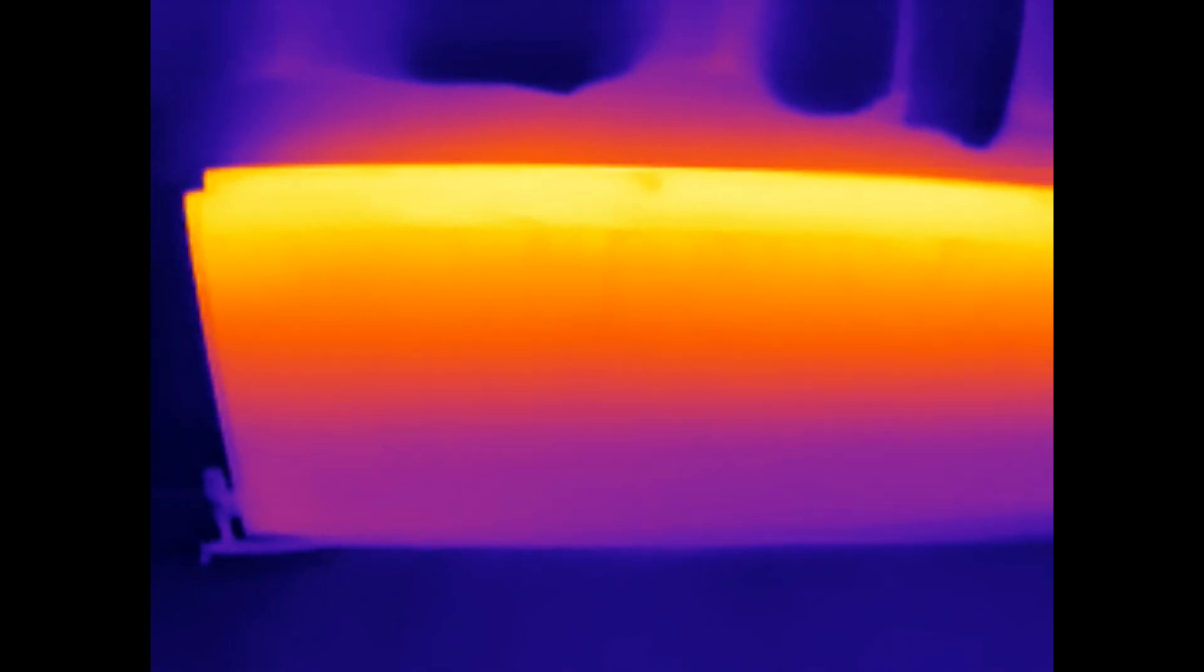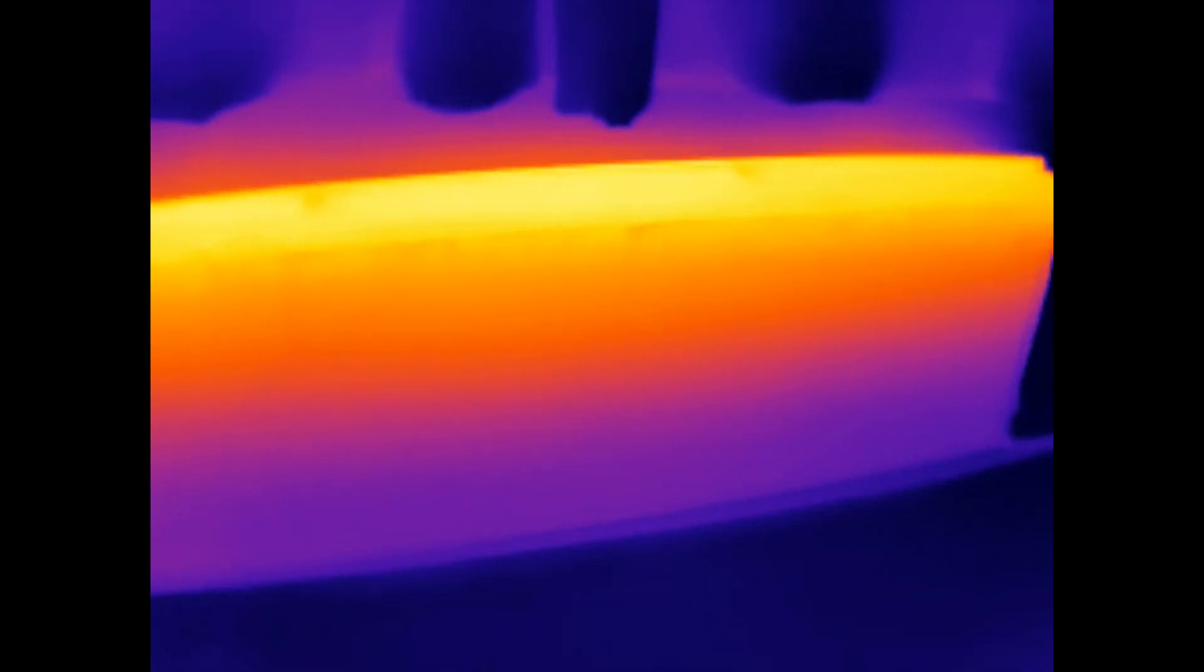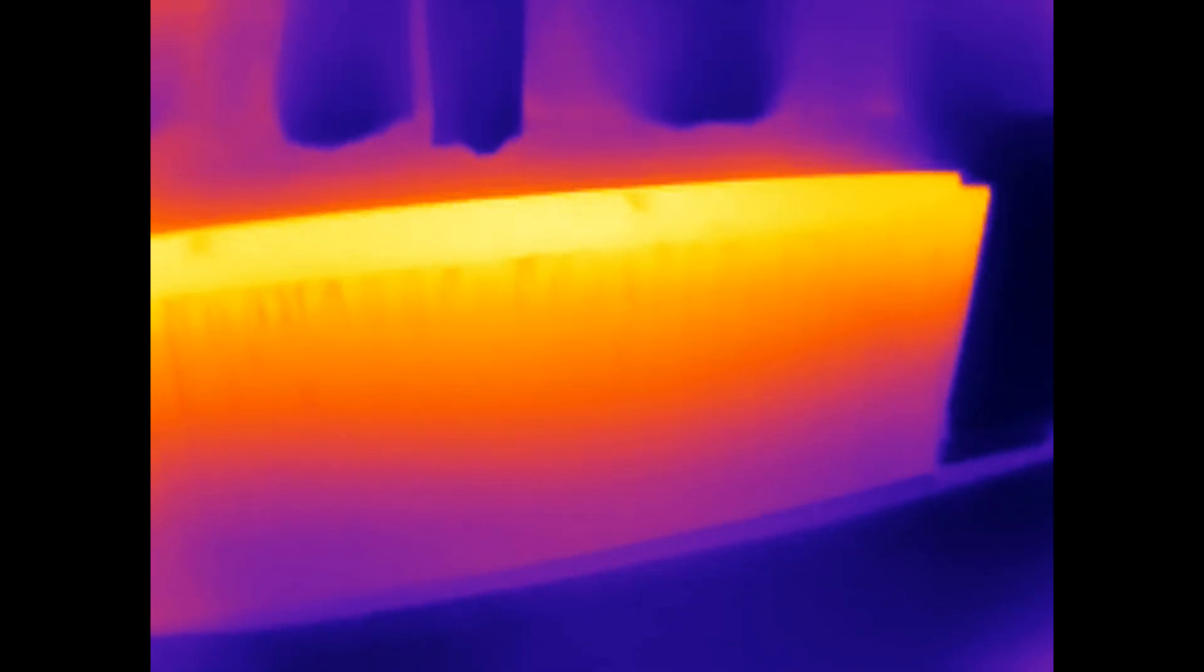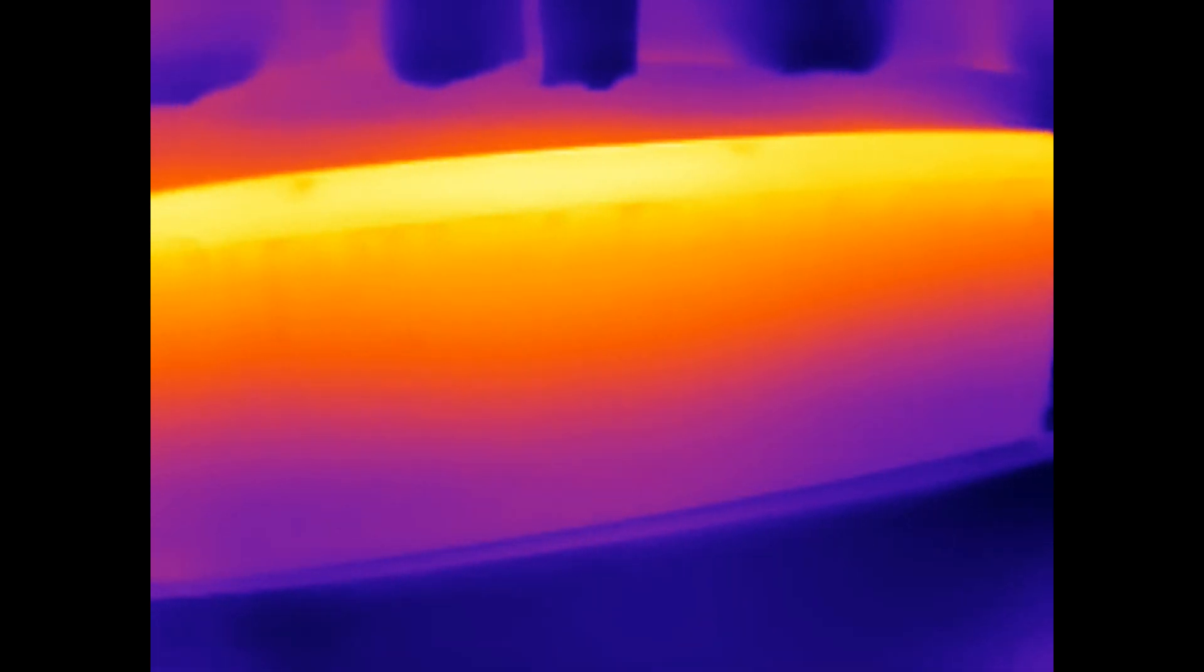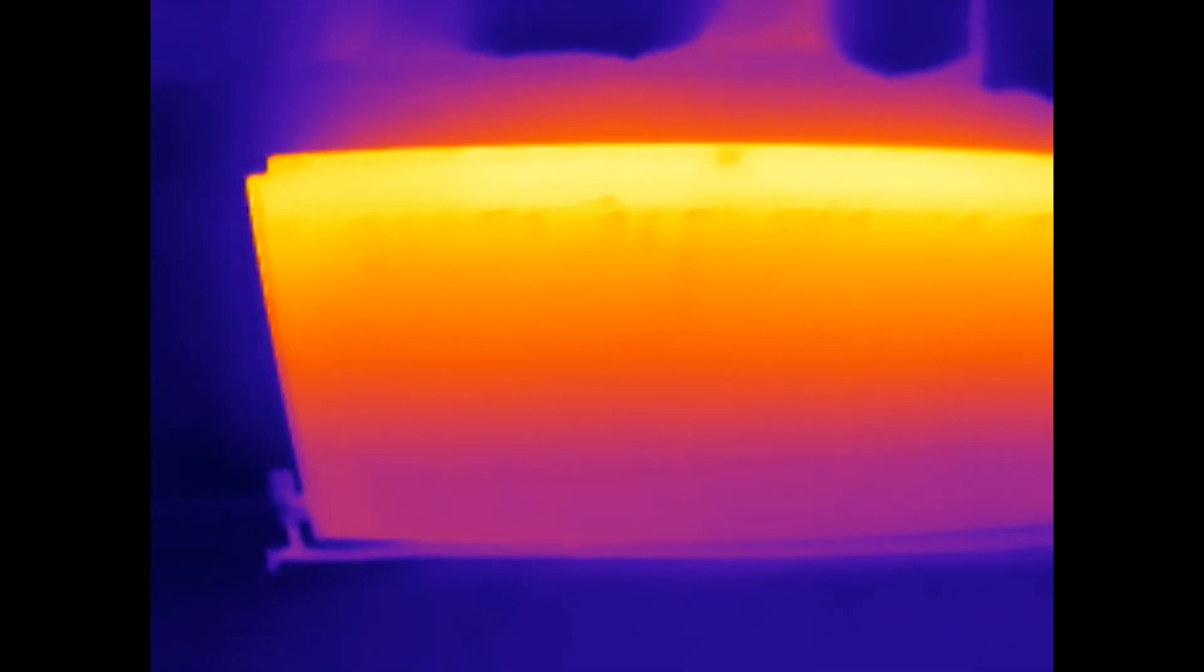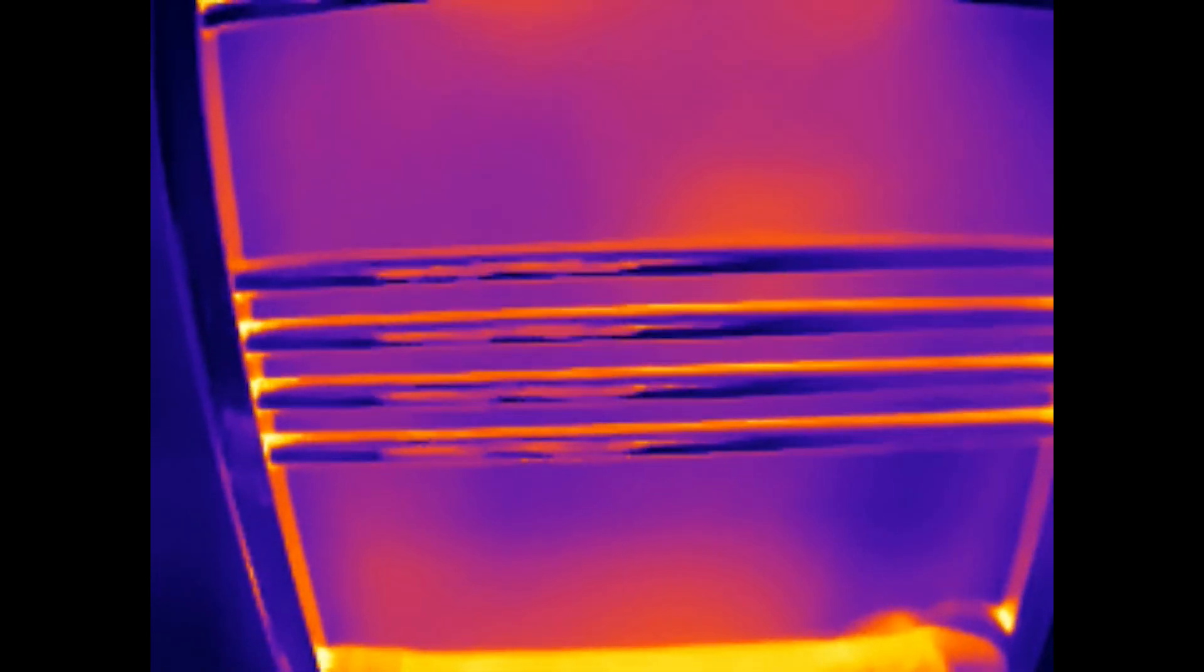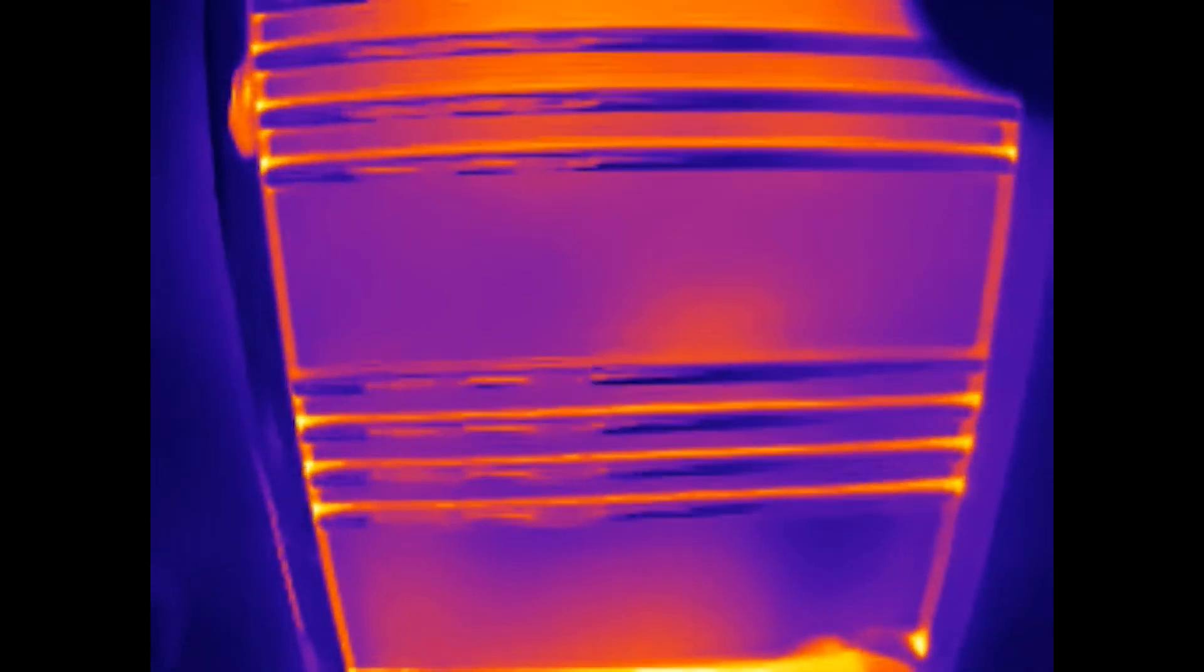I can look at some radiators. These radiators are in the process of cooling down, but you can see the hot water in those radiators is rising up to the top. It's getting to the actual top of the radiator, so we're not getting any air pockets in those.